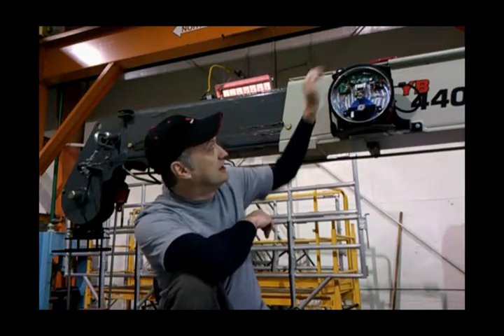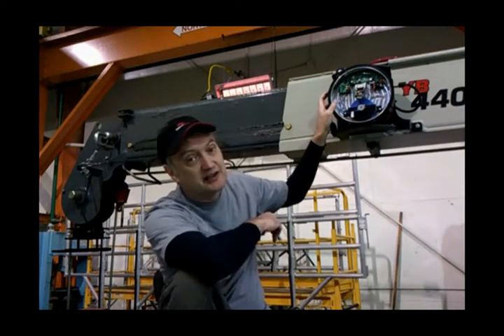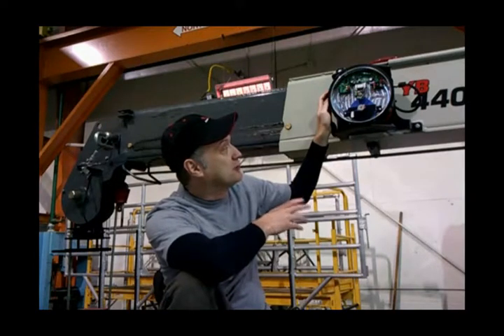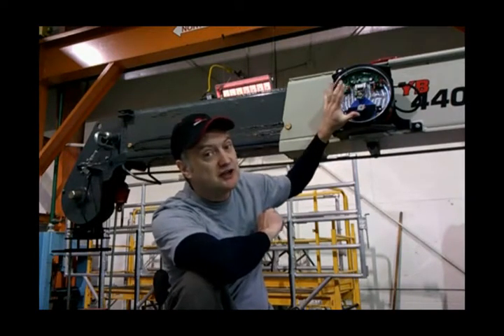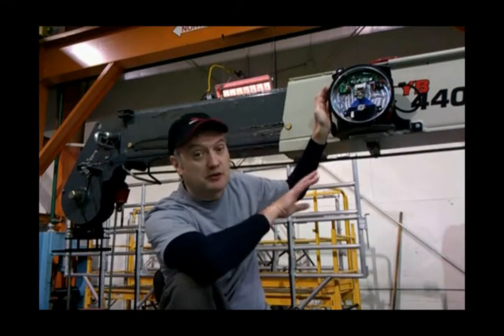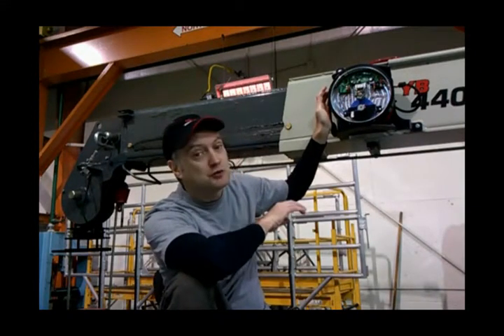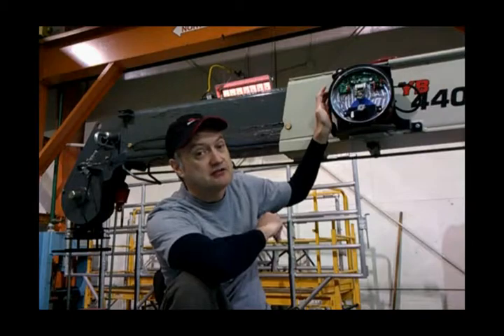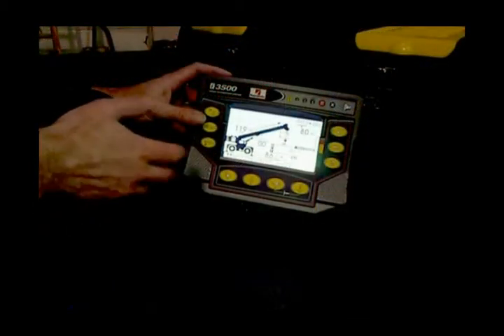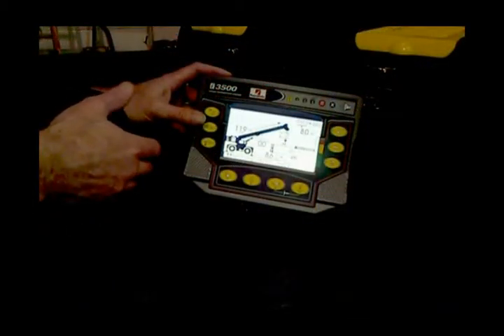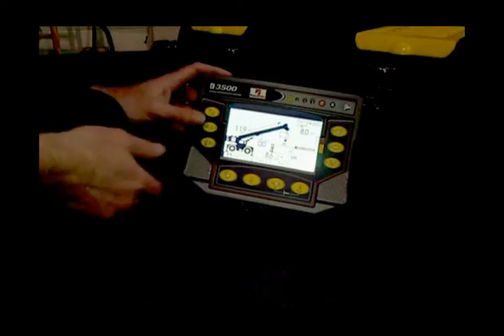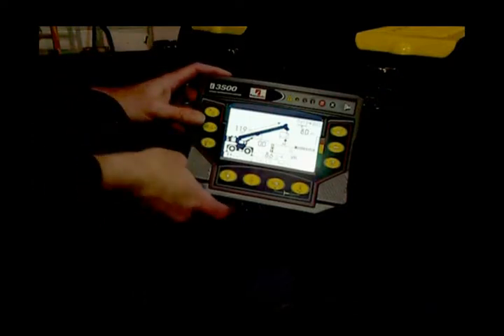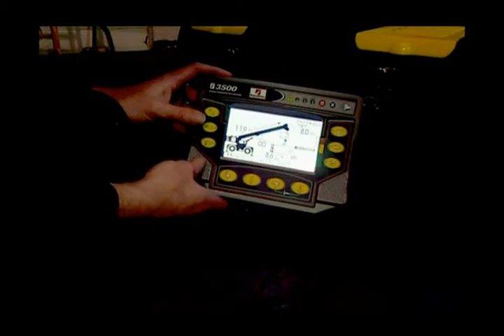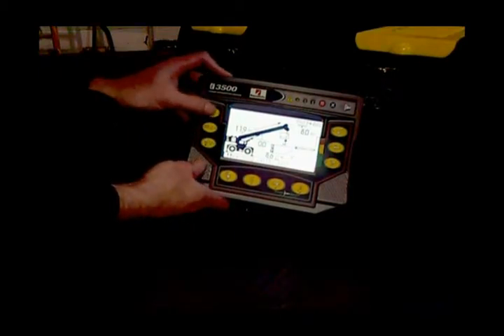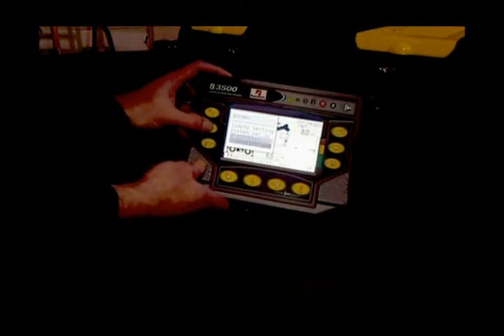circuit board. Now there is a method of making a length adjustment which doesn't require recalibrating if you have not replaced any parts. We're going to discuss that also. But first we're going to go ahead and cover the calibration itself. So let's say we've already replaced our length sensor, which is the potentiometer, or we've replaced the circuit board. What we're going to want to do is begin the calibration process. So we're going to come in and go to Diagnostics and hit the check mark.